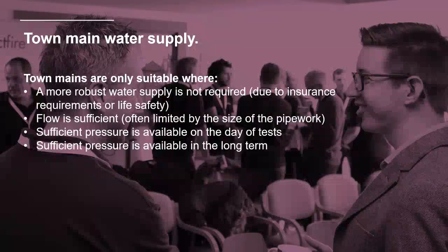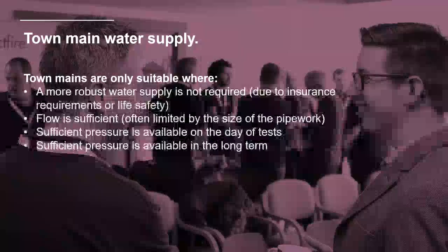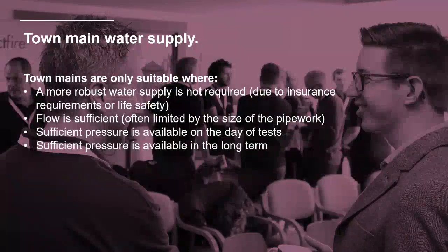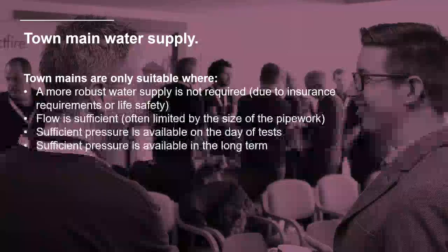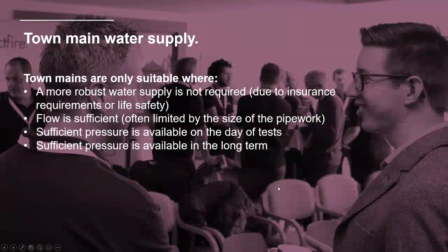And that's a problem, because you want a sprinkler system that's going to last the lifetime of the building. You may end up finishing commissioning and handover, brilliant, and then the next week town main pressure drops. Now the whole water supply is compromised for our sprinkler system. I don't really have a solution to that, but it is a problem in terms of getting a guarantee of long-term pressure availability on the town main.